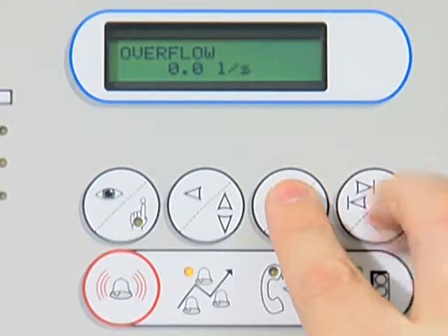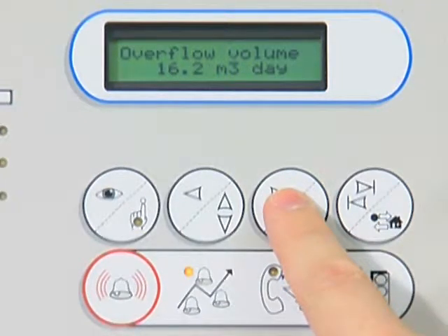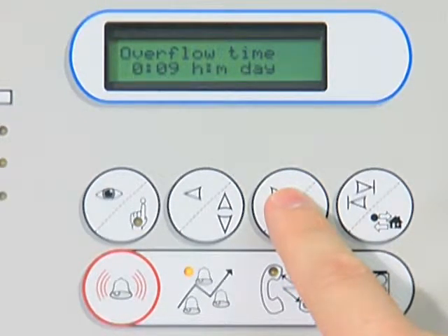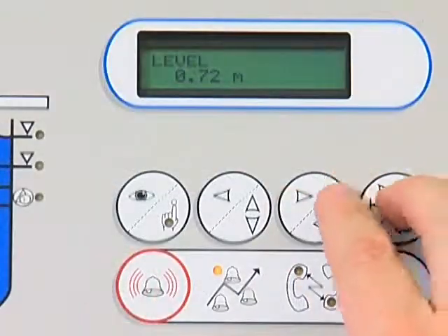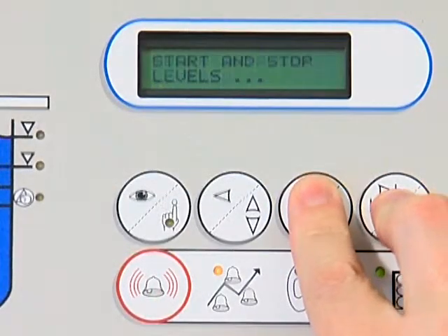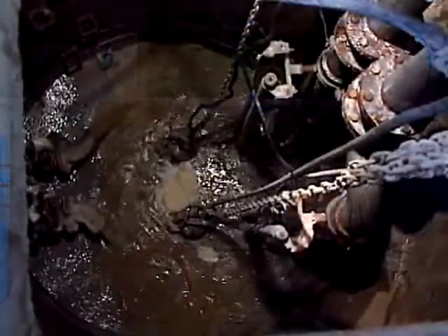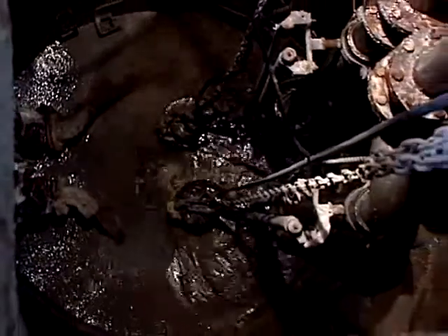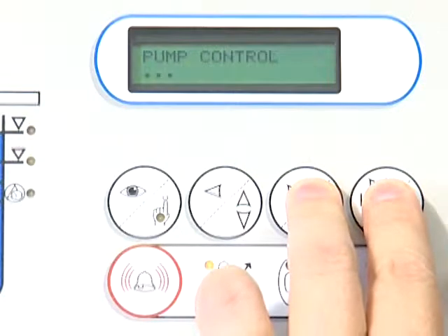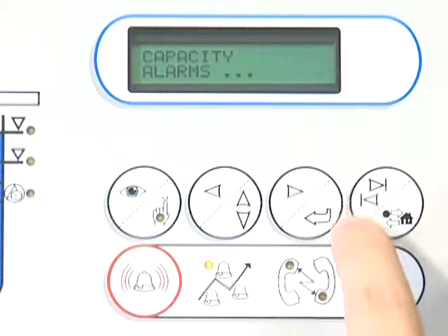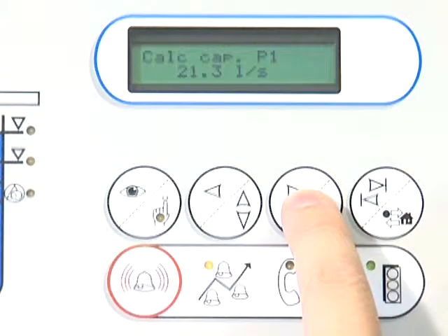Several functions in the FMC control unit contribute to easier maintenance of your pumping station. For example, you can start and stop the pumps at different levels. You can set the maximum pumping time to prevent clogging, and using a cleaning function, you can run the pumps until they're scouring. This function draws off dirt and fat. Other useful functions are current measurement, run time and starts, service, blocking functions, and energy consumption.